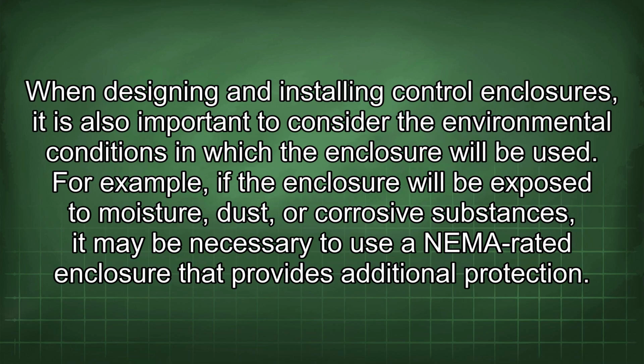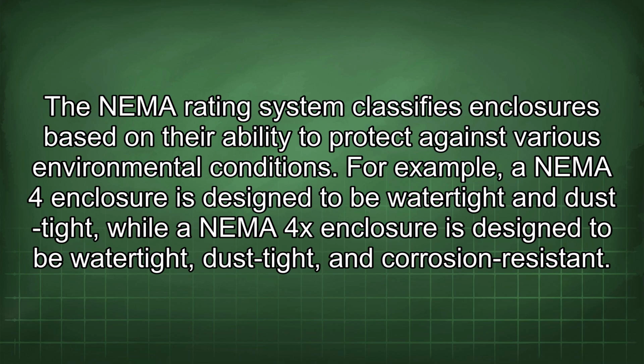When designing and installing control enclosures, it is also important to consider the environmental conditions in which the enclosure will be used. For example, if the enclosure will be exposed to moisture, dust, or corrosive substances, it may be necessary to use a NEMA rated enclosure that provides additional protection. The NEMA rating system classifies enclosures based on their ability to protect against various environmental conditions. For example, a NEMA 4 enclosure is designed to be watertight and dust-tight, while a NEMA 4X enclosure is designed to be watertight, dust-tight, and corrosion-resistant.